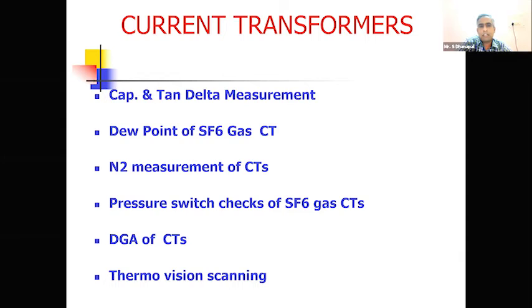If you see instrument transformers, these are testing we are doing - for example, capacitance and tan delta measurement we are doing, but we are only on offline measurement. That should be a technique which is very simple, economical and robust, where one shot result should come on screen. SCADA systems are available now for monitoring parameters, but what is happening inside the transformer, inside the CT, inside the voltage transformer, inside the breaker - that we are not able to see as an online X-ray. That is still lacking, and that's what is required in the modern day power sector context. That's what we actually want.